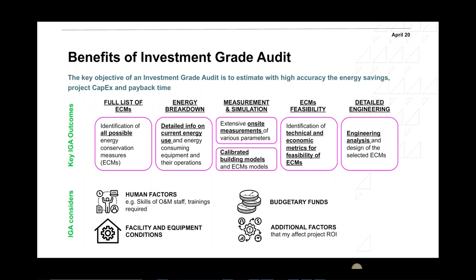Also, you need to check with maybe more than one supplier, so you didn't go with only one supplier, and have at least more than one quotation. And you would need to do some engineering analysis, preferably at least at a schematic level, to show how things will be installed. Now, there are some other IGA factors that need to be considered, like human factors, the skills of O&M staff. Let's say you're adding an absorption chiller, you would probably need additional staff members that have the required expertise to run the system.